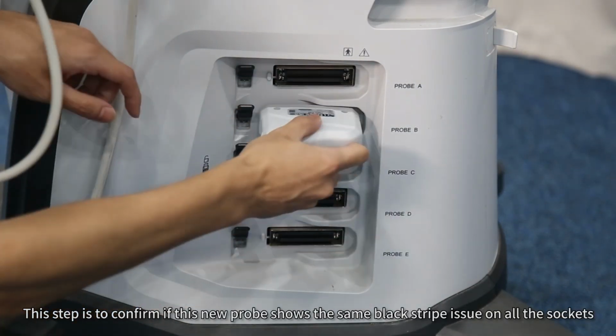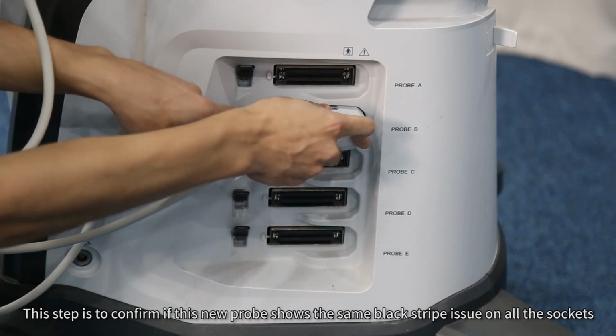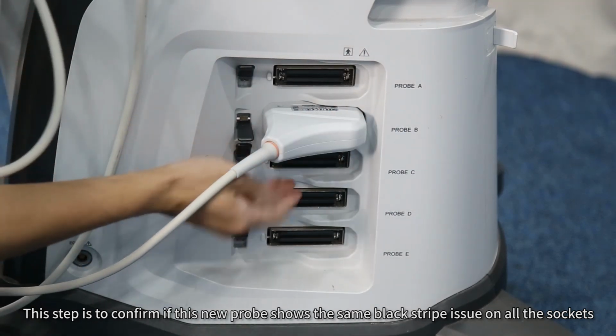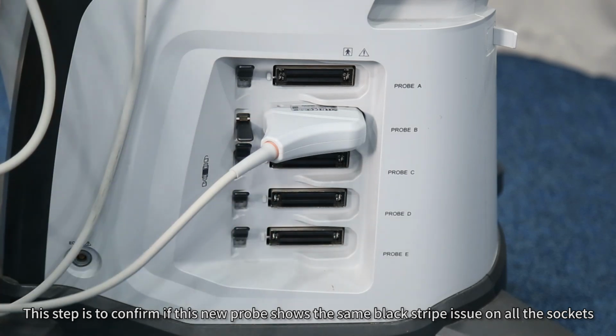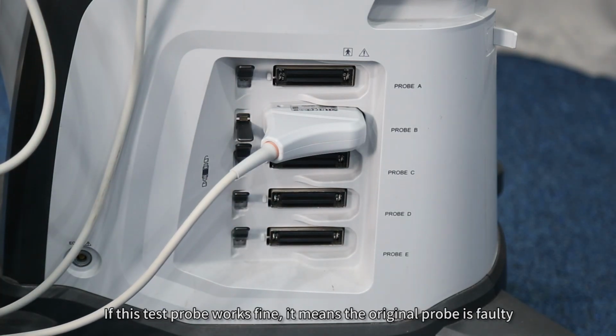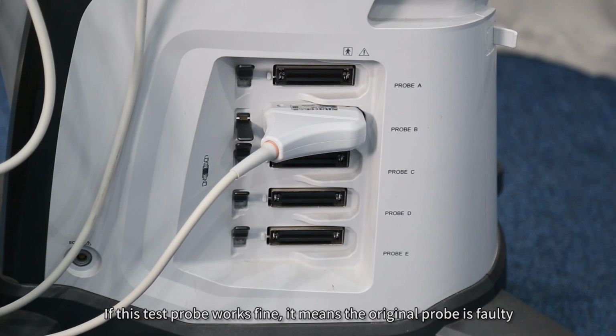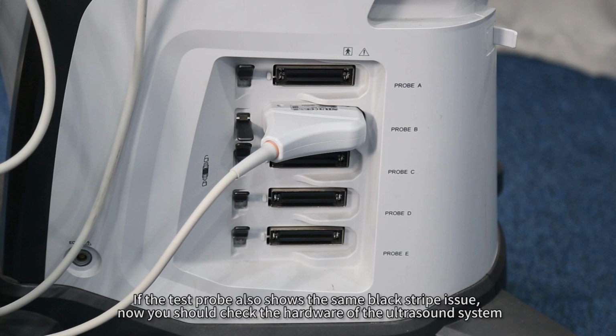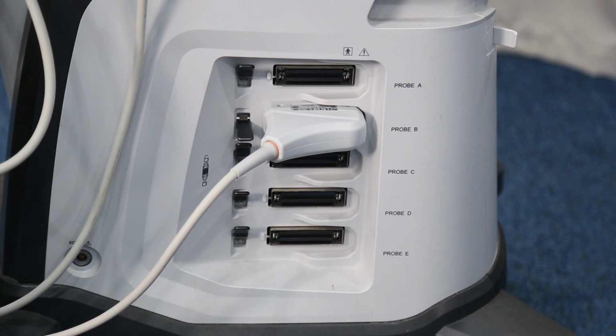This step is to confirm if this new probe shows the same black stripe issues on all sockets. If this test probe works fine, it means the original probe is faulty. If the test probe also shows the same black stripe issues, now you should check the hardware of the ultrasound systems. The demonstration for this troubleshooting is finished.